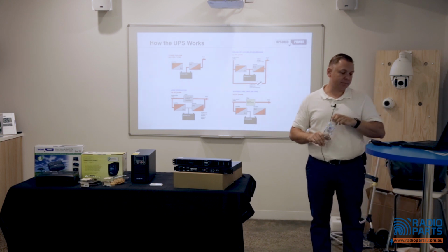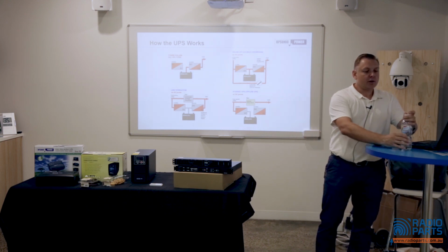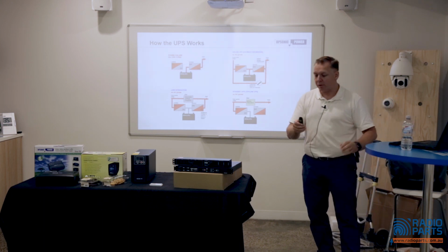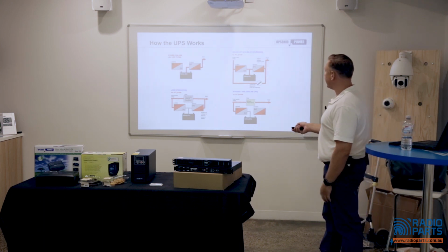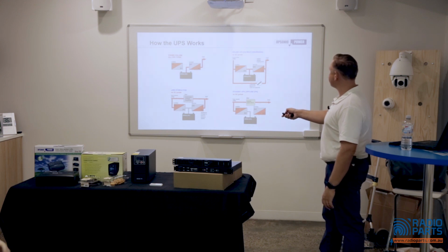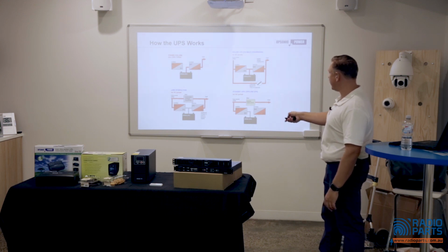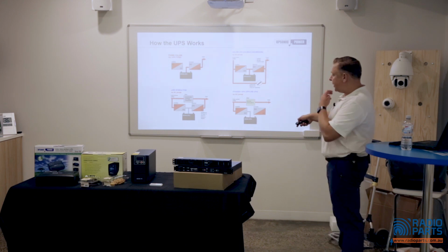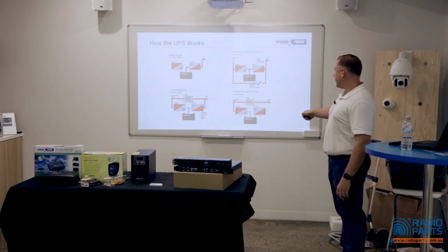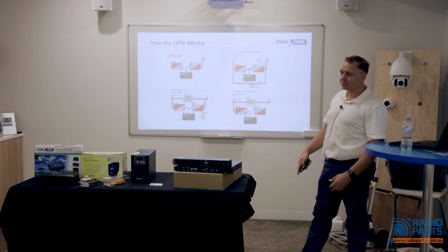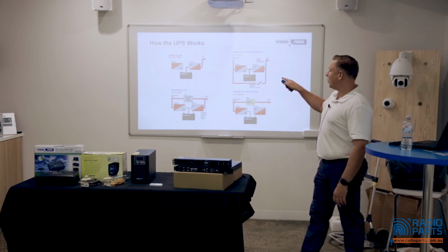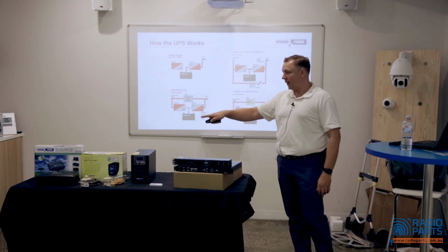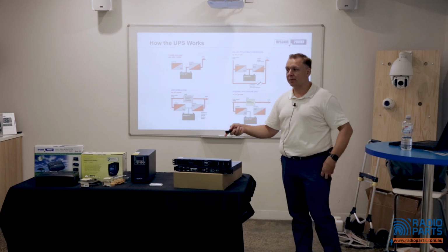Okay, how a UPS works. Most UPSs have pretty much the same sort of components. So we talk about our line interactive, our standby that we talked about before. We have a rectifier, an inverter, and a battery. This part of it is a filter in this case, or an automatic transfer switch when we get to an online unit.